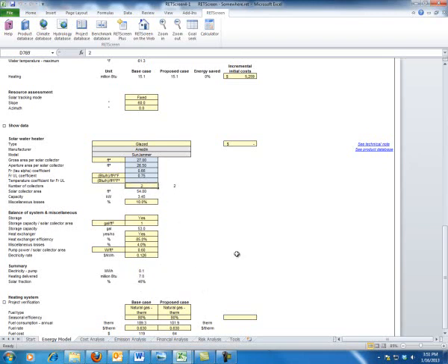I personally have these older solar thermal panels. I put them up and that brings my value up to 78%. Now I'm going to take miscellaneous losses at 10%. It should be about 2% per solar thermal panel that's mounted somewhere, so I'm going to leave that at 10. And then I'm going to say, okay, I need 132 gallons minimal.